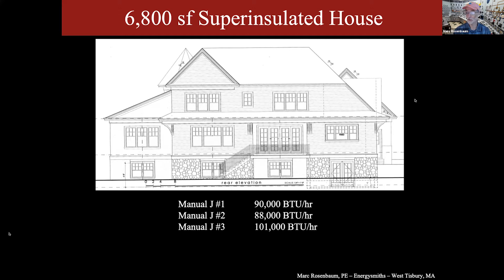I sent them back and said no. They had a proposal for a mechanical system that was 11 tons of heat pump on this project. So I said, you need people who really can do manual J and specialize in that. They brought back someone else who was close, only 2,000 BTUs an hour less. I said, let's try one more time. And we got 101,000. So, at least we have consistency.